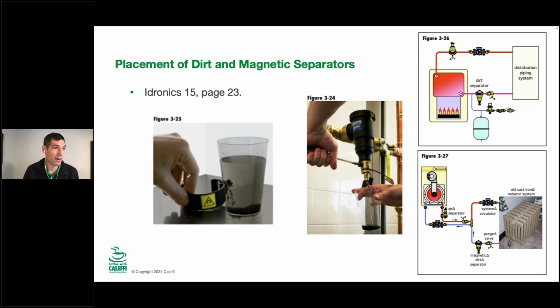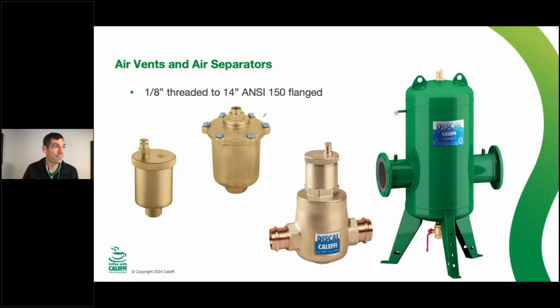If you still have buckets of magnetite over and over, that may just be the case. If you have old cast iron radiators that will never really seal completely, that may just be something you fight with forever. Otherwise, you might have a leak somewhere that you can't see. You want to turn off that autofill valve and see if you can find it, so you're not just bringing fresh oxygen into the system to keep rusting away your components forever.